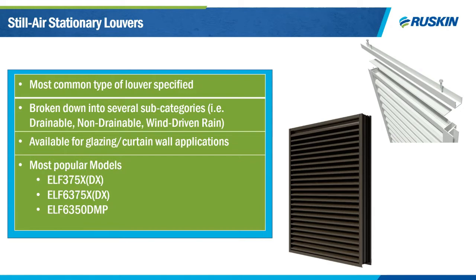The most popular models Ruskin offers are our ELF 375X and DX, our 6-inch ELF 6375X and DX, and our 6-inch ELF 6350 DMP. While all offer excellent performance for their louver class, the ELF 6350 DMP offers the best performance in the industry — 62% free area in its tested size, maxing out at 1,250 feet per minute free area velocity. No other louver in the industry meets both of these requirements. This will be the most expensive of the group with the highest performance, while the ELF 375X and DX offer great performance with the best economy.